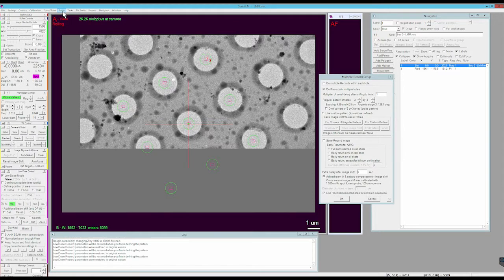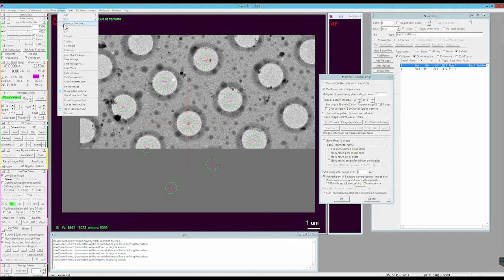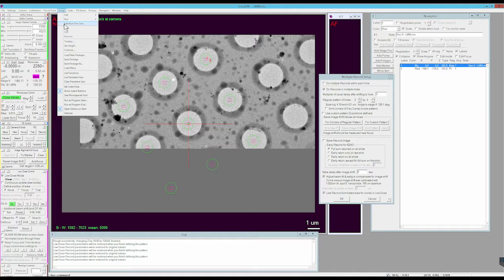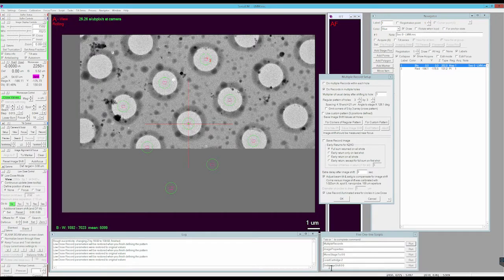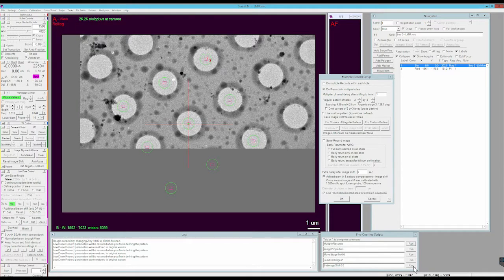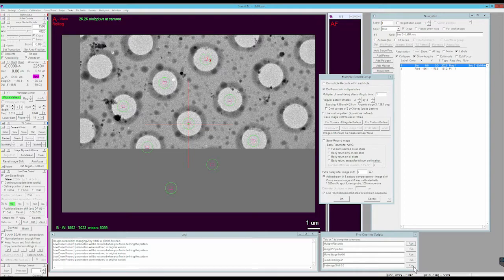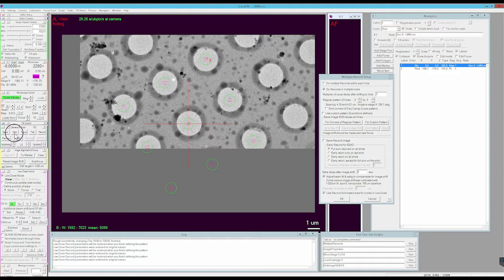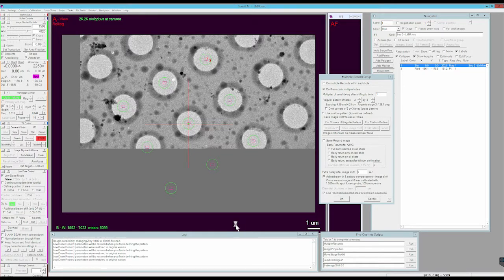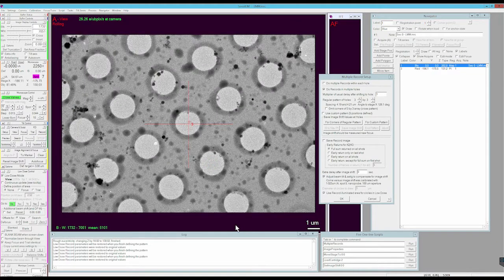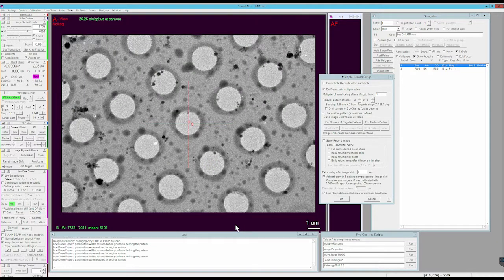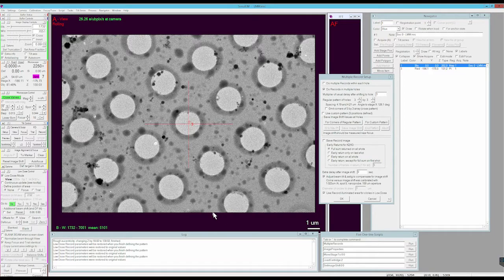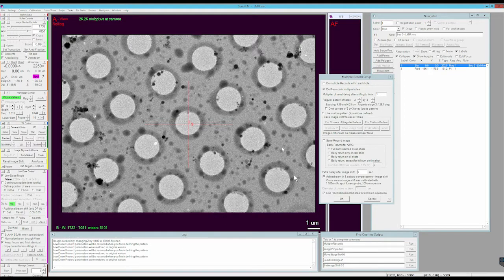To do that, we can go script, edit, run one line and then set image shift 0, 0, run. When I click this button, the image shift will be returned to 0 and taking a view image will refresh the view. Now my stage and image are aligned with each other back to where I originally was.